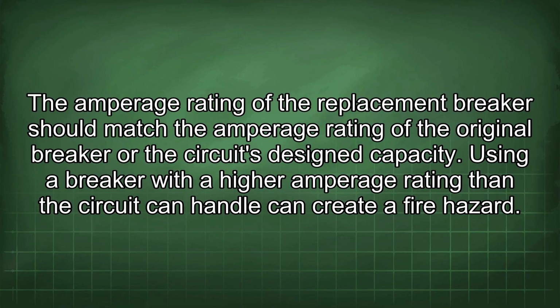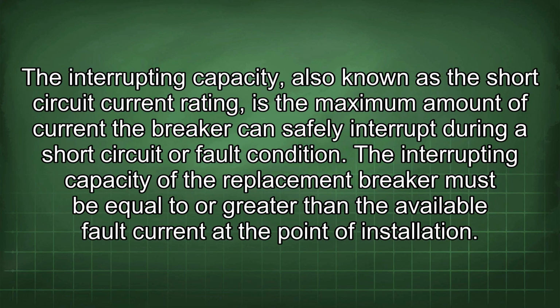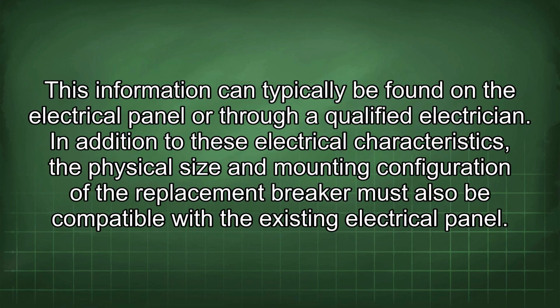fire hazard. The interrupting capacity, also known as the short circuit current rating, is the maximum amount of current the breaker can safely interrupt during a short circuit or fault condition. The interrupting capacity of the replacement breaker must be equal to or greater than the available fault current at the point of installation. This information can typically be found on the electrical panel or through a qualified electrician. In addition to these electrical characteristics, the physical size and mounting configuration of the replacement breaker must also be compatible with the existing electrical panel.